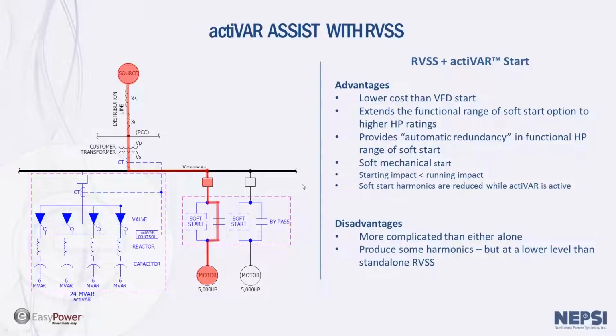So the advantages of this system are it has a lower overall cost when compared to a VFD start project. It extends the functional range of the horsepower range that the soft start can be used in. Typically, when you get to the 4,000 or 5,000 horsepower range, a soft start no longer operates because the voltage is too low at the motor. You don't have sufficient torque to start. The actiVAR can be sized to help the soft start and extend that range further to higher horsepower ranges, and of course save money.